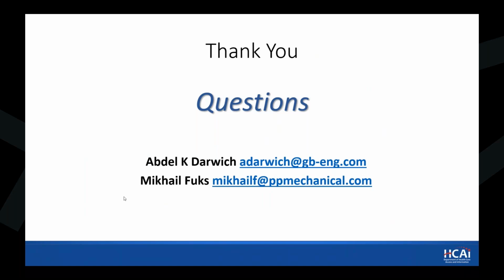You're correct. In Guideline 44 we have a detailed equation if you want to go into the details and estimate this. The key metric, as I mentioned, is one that's not easy to obtain from the filter manufacturer: the dust holding capacity. You can obtain it, but it's not a readily published metric, and it tells you how much a filter can take before it fails. You can use that in the equation to estimate, but it comes back to pressure drop. When you have wildfire smoke, your normal change-out schedule of 3 or 6 months won't apply anymore, unless you're very far from the fire and have a good wind direction that isn't affecting your outside air intake. Otherwise, we recommend checking your filter very frequently during a wildfire smoke event.